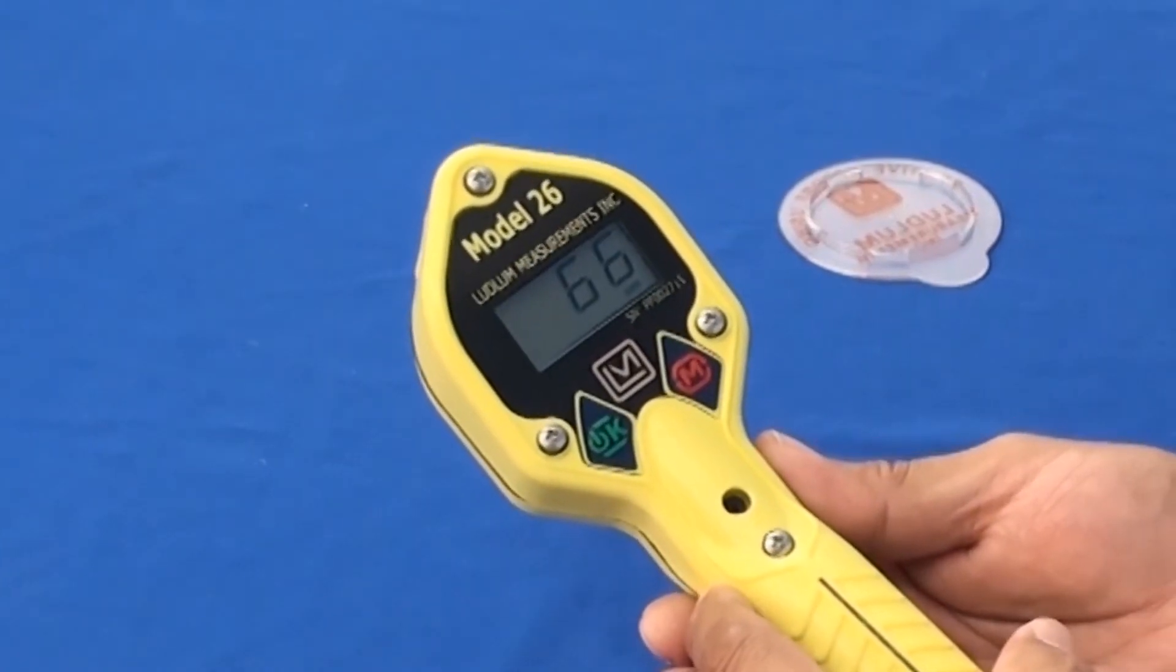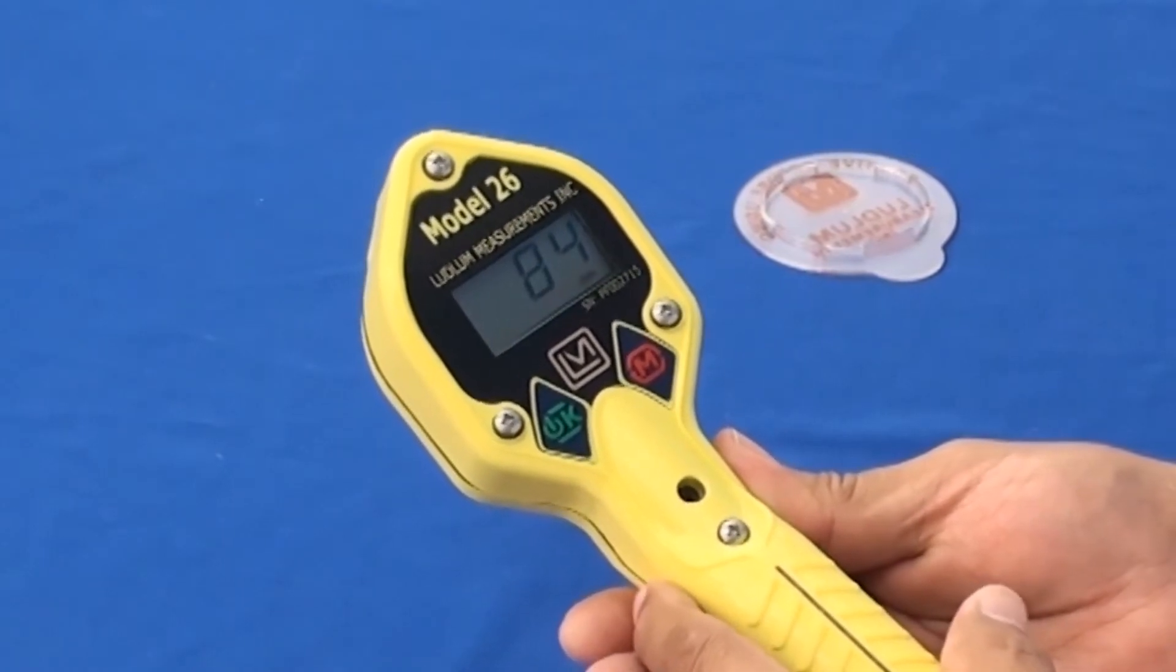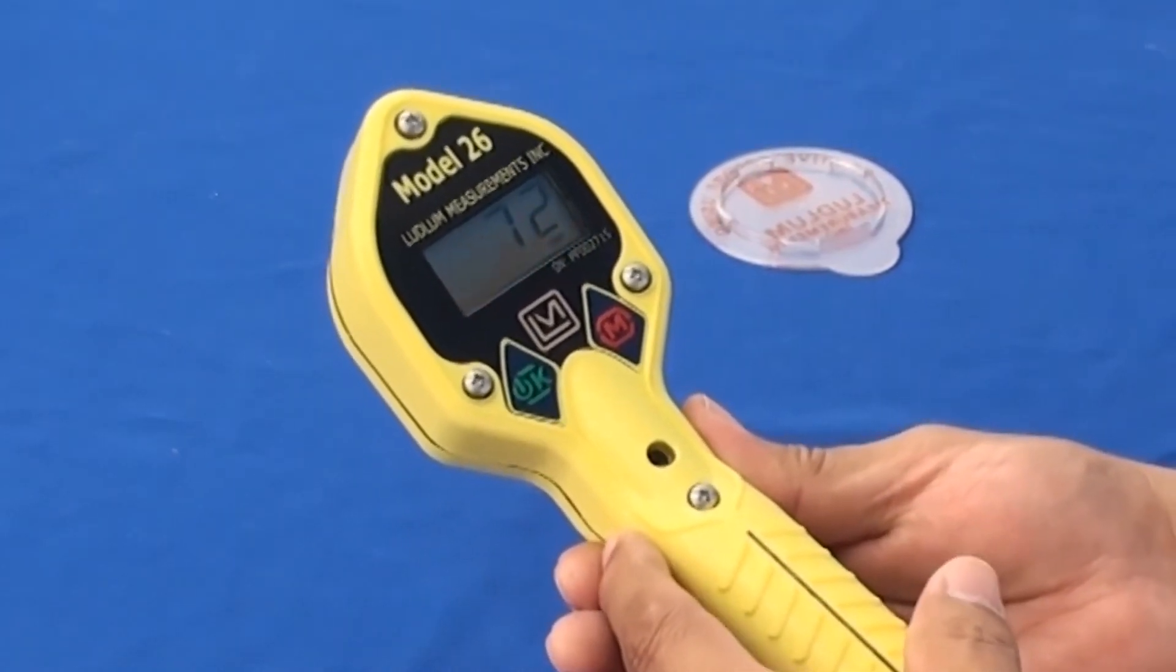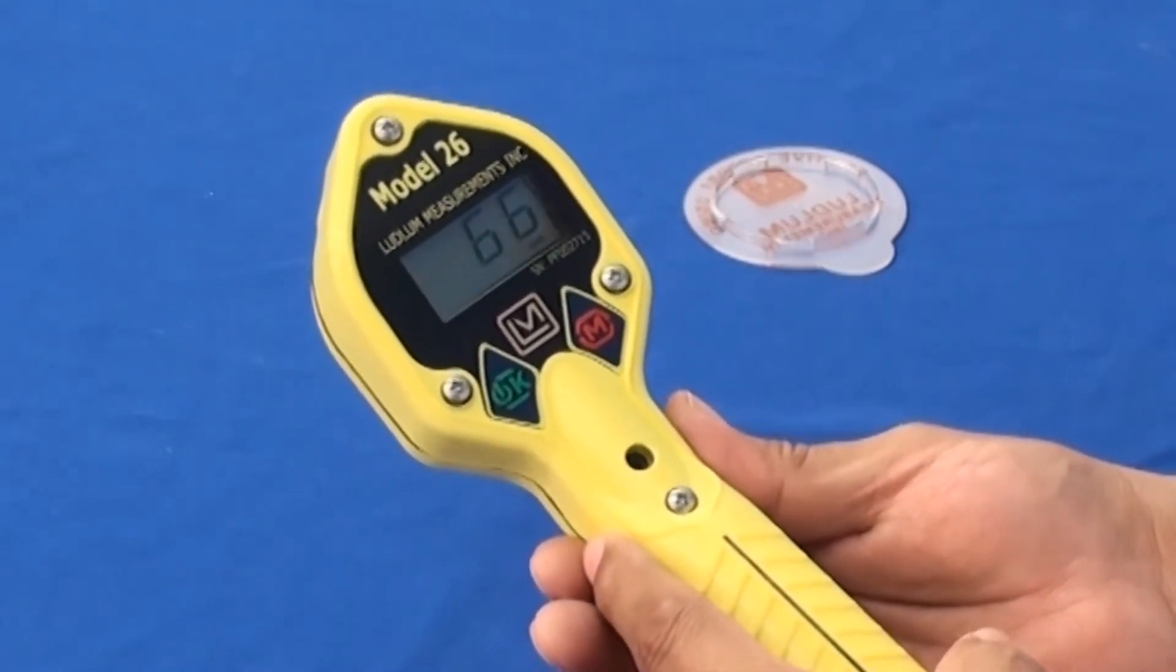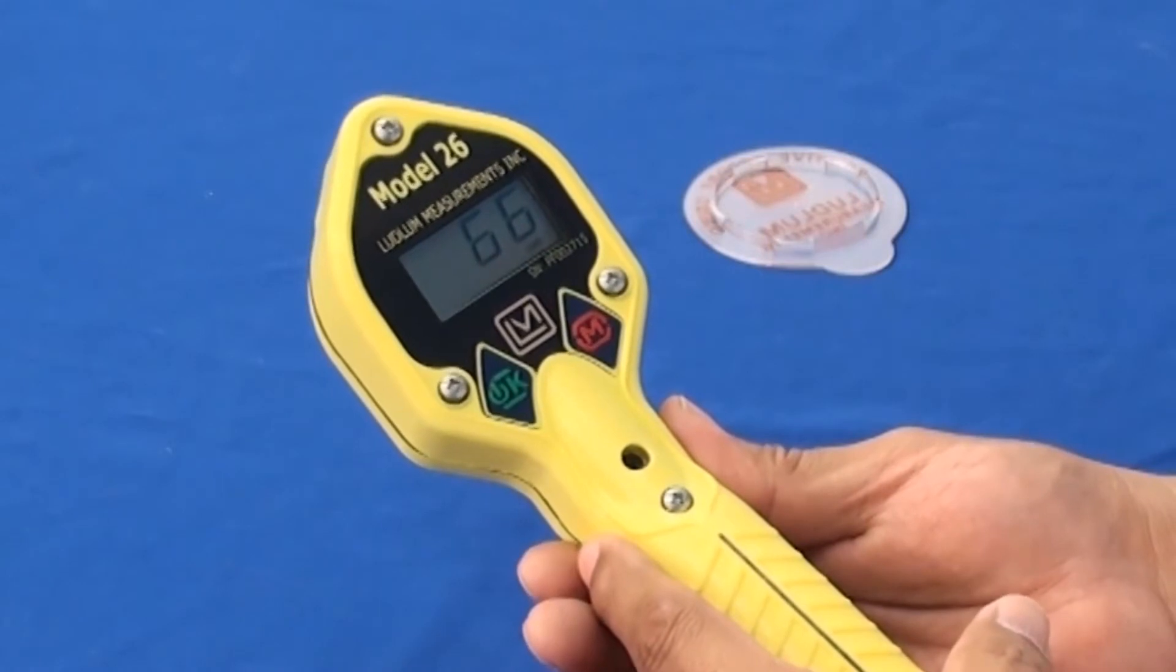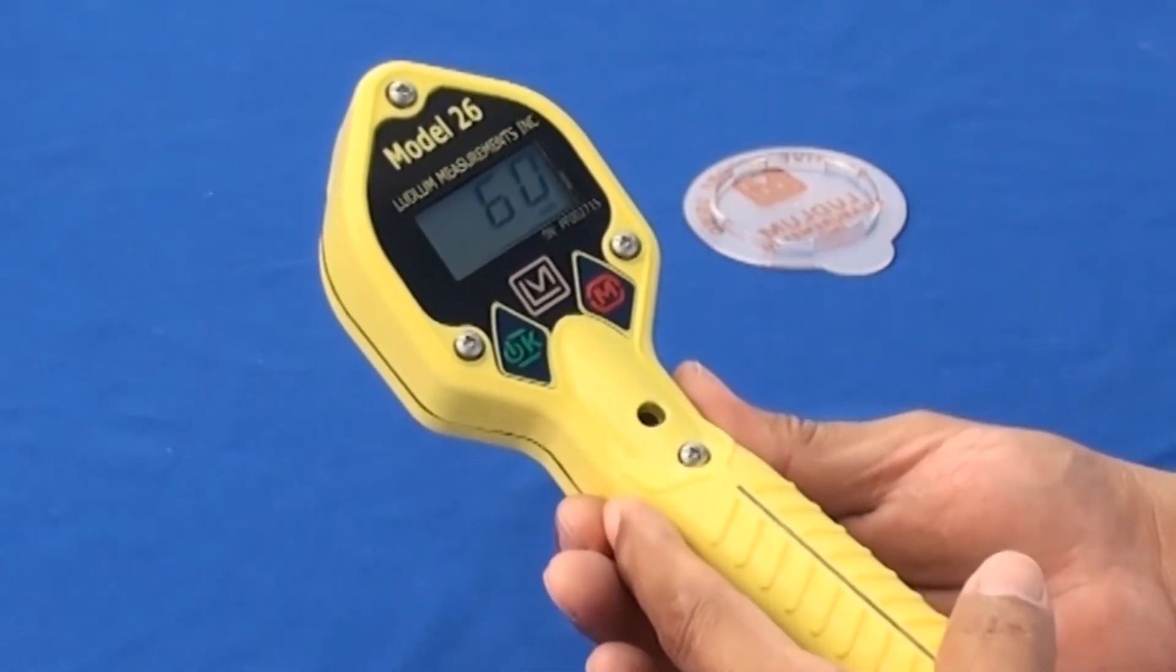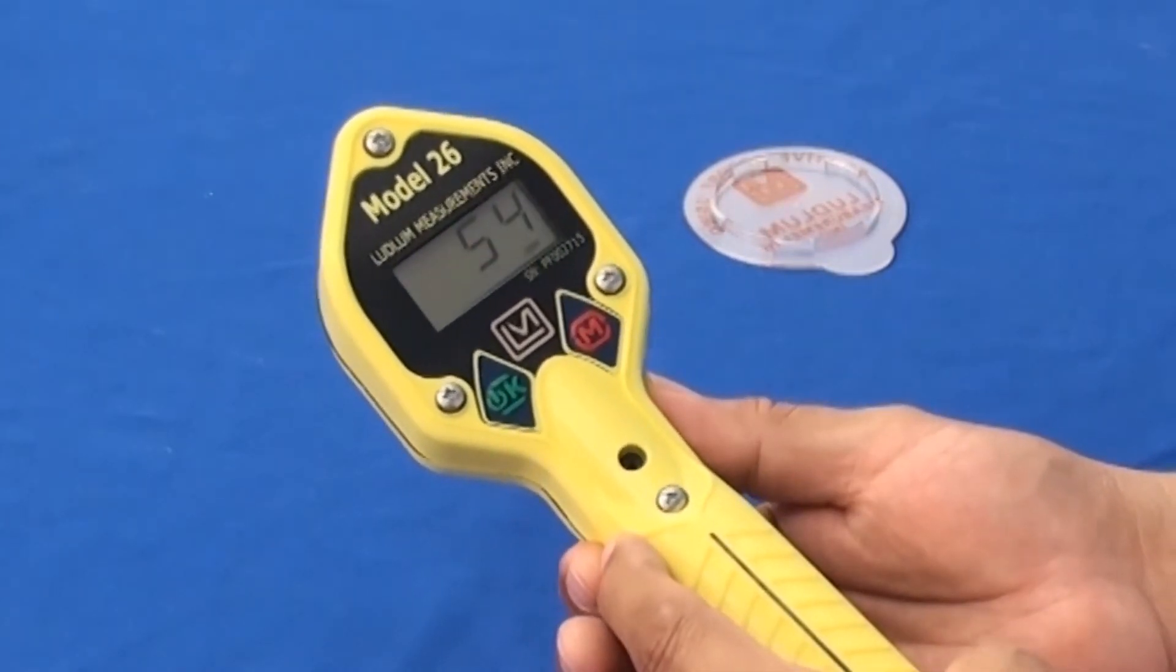That backlight can be set to stay on all the time. Refer to the user's manual which will show you how to properly disassemble the model 26 to access the two pole dip switch that's located on the main board alongside the pancake tube.